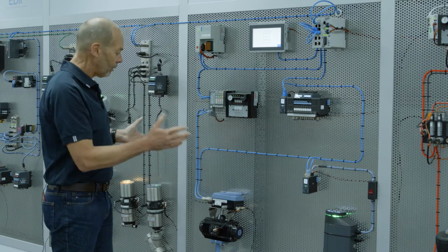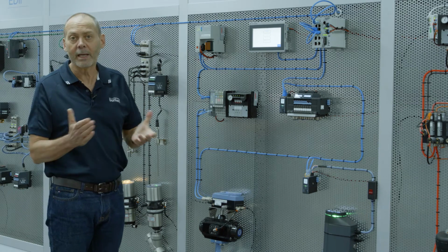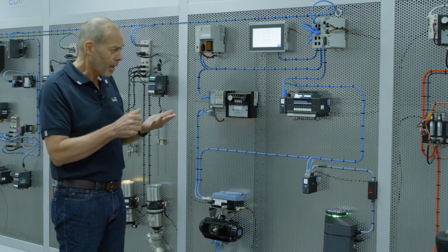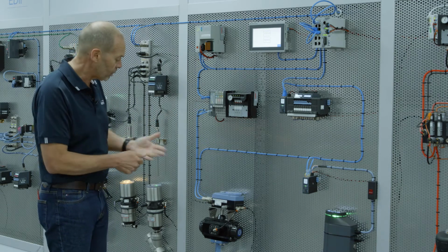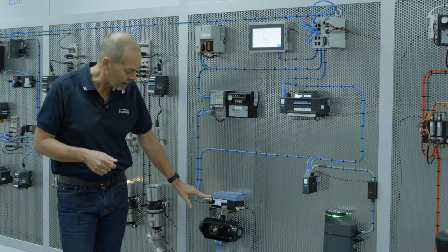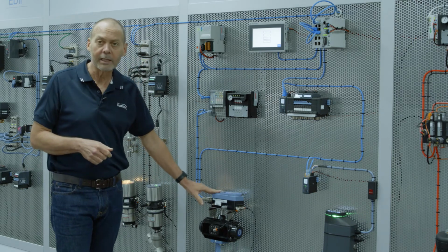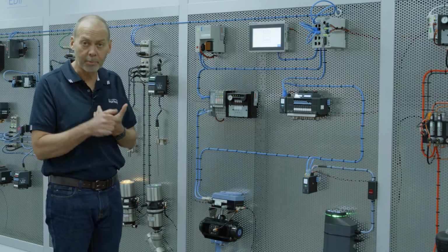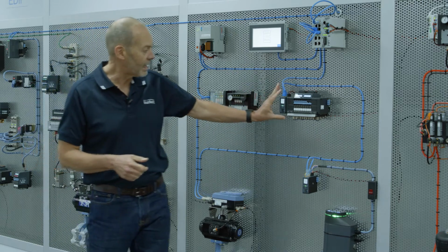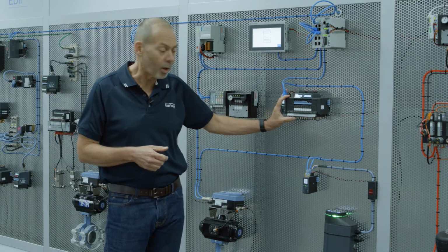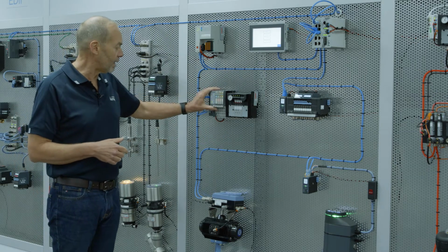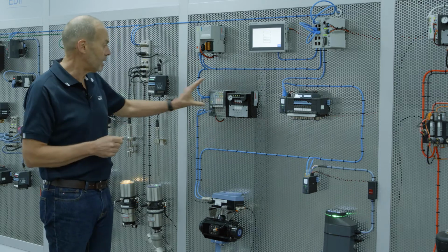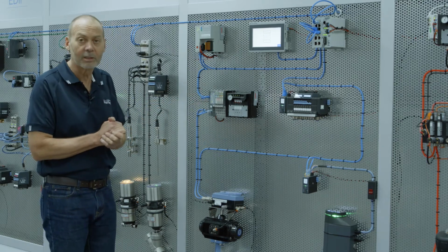So in this ring, and with Ethernet in the field, there are three different ways that we can connect to devices in the field. And that is via direct connection, which we've demonstrated here by connecting this modulating butterfly valve directly to the EtherNet IP. Alternatively, we can go through I/O blocks. We have a couple of examples here. One is a pneumatic block manifold, and the other one is the integration that Burkert has with Rockwell and their point I/O system. This integration is around 15 years old, and it's still quite current.